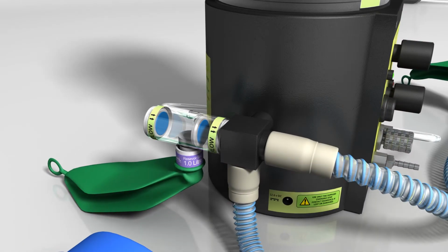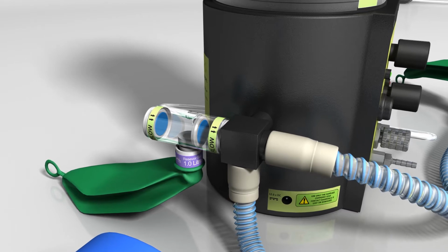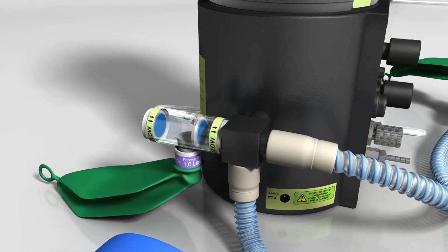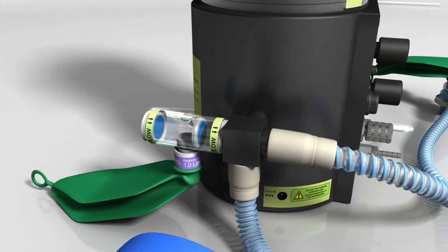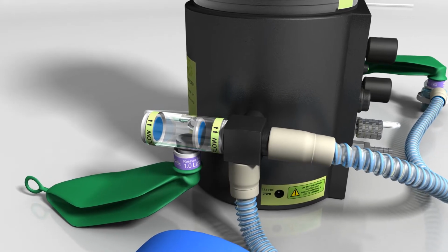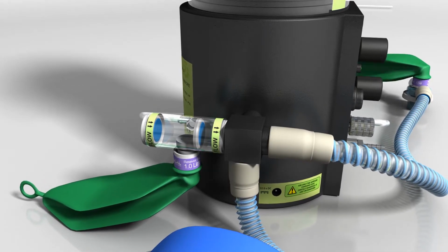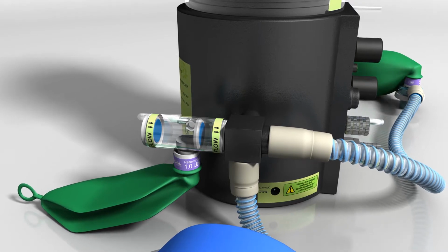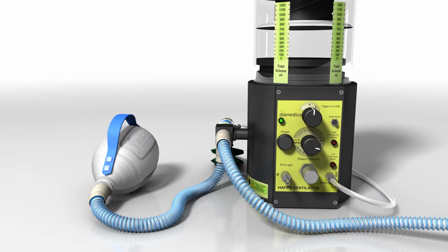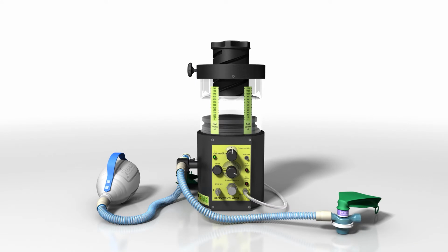There is a circuit block fitted to the side of the Helix ventilator. The gas flow in the circuit works by entraining air through the one-way valve at the back of the reservoir block. This is either controlled by the patient's own inspiratory effort when spontaneously breathing, or by using the self-inflating bag or mechanical ventilation when required.